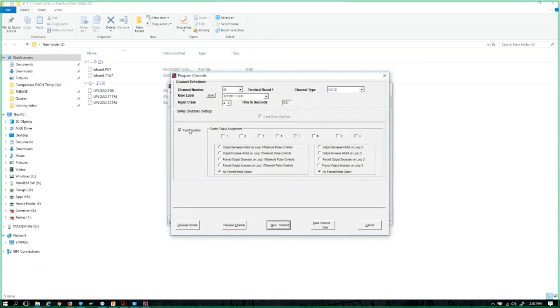Now, this is the most important thing on this whole screen, fault condition. I had a gentleman one time call me up and he said, I'm not shutting down on any of my channels. And after spending a little time over the phone with him and reviewing his program, we discovered that he went in and he misinterpreted what this meant. He was novice to the system and he unchecked all of these. So if you want the unit system to fault and shut down if this channel is triggered, you definitely want to make sure that fault condition is checked on a discrete channel.